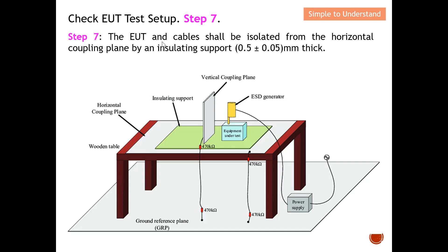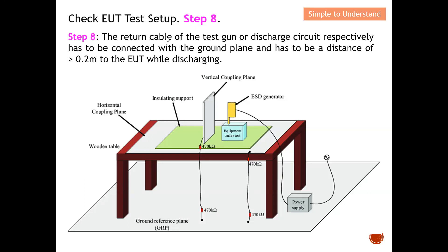Step number seven: the EUT and cables should be isolated from the horizontal coupling plane by an insulating support approximately 0.5 mm thick. This insulating support provides separation between the horizontal coupling plane and your EUT or DUT.